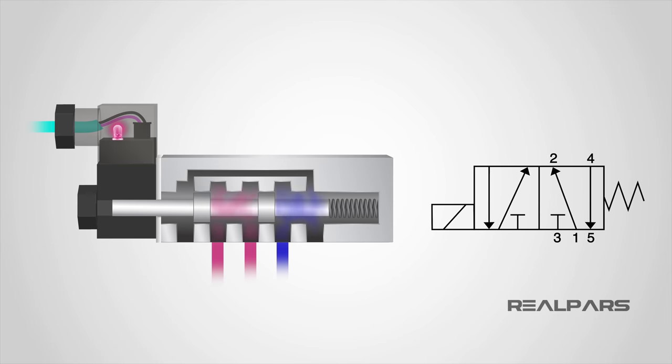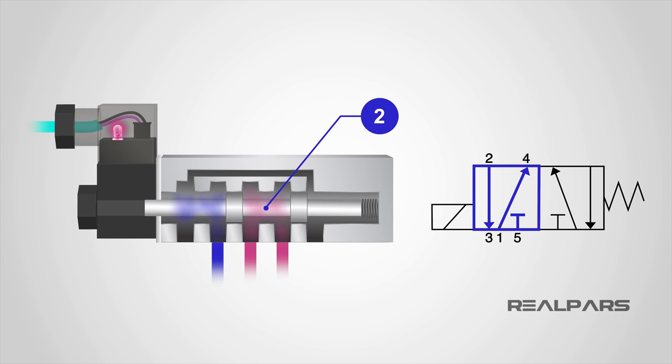When we see a valve schematic, we can see it is made up of boxes, each containing a number of lines and arrows. The number of boxes that make up a valve symbol indicates the number of possible positions the valve has. Flow direction is indicated by the arrows in each box. These arrows represent the flow path the valve provides when it is in each position.